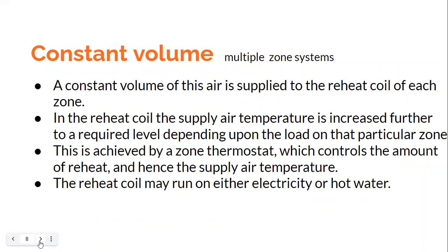So you are supplying a constant volume of air to each zone because it is a constant volume system. But then how do you vary the zone temperatures? You are supplying from a central AC plant a constant volume of air, right? Then if you want to maintain different temperatures, you need to put in a reheat coil for each zone. In the reheat coil, the supply air temperature is increased further to a required level depending upon the load on that particular zone. So this is how, by supplying a constant volume, you still maintain multiple zones, multiple temperatures.